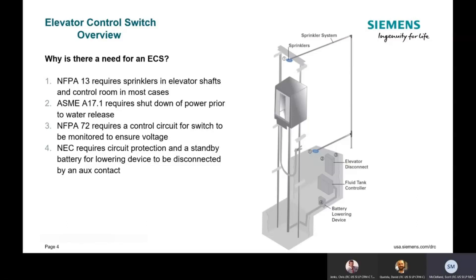After a certain time, the power will then turn off to the elevator via the shunt trip on the elevator control switch. Lastly, once there's confirmation that there's no power to the elevator, the fire alarm panel will then send a signal to the sprinkler system to turn on to extinguish the fire.